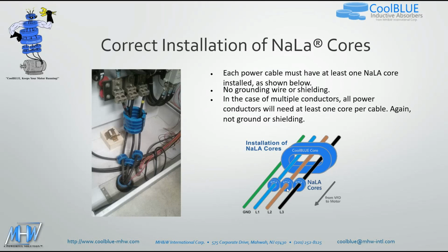The NALAs are always installed in the direction of the motor. So if the VFD is up here, the order of installation is CoolBLUE and then the NALA, as shown in the picture here. Here's your VFD, you got CoolBLUE and NALA. That's the preferred arrangement.